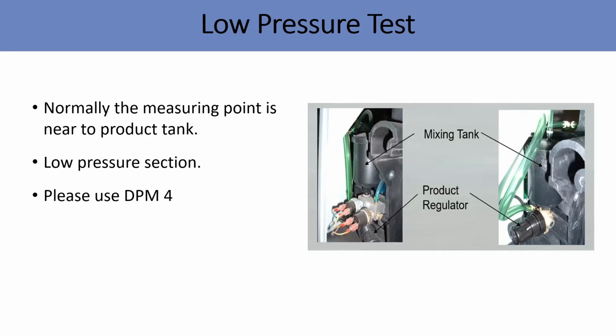And low pressure is basically measuring near the flow line. So you are checking the low pressure section near the mixing tank and product regulator. These two measurements, high pressure and low pressure, are normally done if your checklist reading on oxygen purity is not in the range. If the range is not good and you get an alarm, you need to do this test to verify whether there is any leakage at the low pressure point or the high pressure point, or too much pressure. So you need to check this particular point.